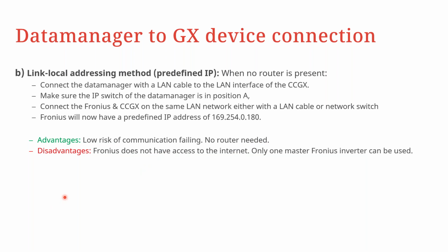The biggest advantage here is that you have low risk of communication failing, so no router is required. But the disadvantage is that the Fronius inverter does not have internet access. And in addition to that, only one master Fronius inverter can be used when you're going through the link local addressing method.